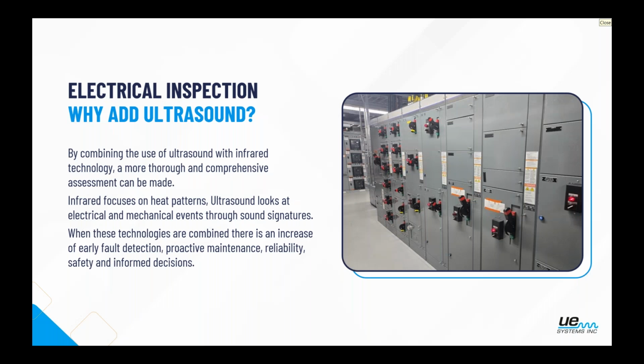Perfect. All right. So as far as for those of you that aren't using ultrasound for an electrical inspection, I guess one of the main things that you're probably looking for is, why? Why would we start doing this? If we're already in compliance, if we're already having infrared inspections done at least annually, ideally more often than that, why include ultrasound? So the idea of it is, as the topic of this conversation, a holistic approach. There are things that ultrasound will be able to inspect for that infrared would not be able to pick up, and vice versa. One does not replace the other. They work together to have a more thorough and in-depth inspection.